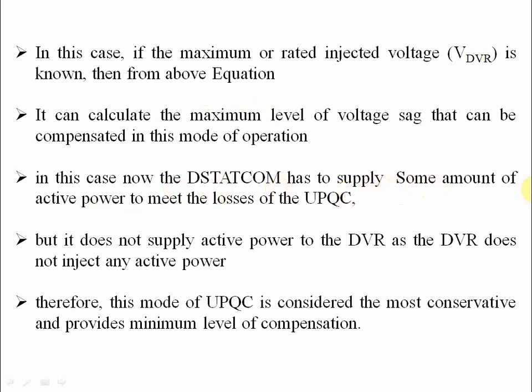In this case, the DSTATCOM has to supply some amount of active power to meet the losses of the UPQC. So the DSTATCOM will come into picture and supply some active power to compensate the UPQC losses. However, it does not supply active power to the DVR, so the DVR does not inject any active power. Therefore, this mode of UPQC is considered the most conservative and provides the minimum level of compensation.